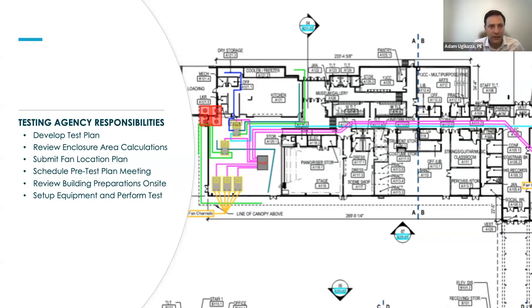So in that background in the slide, you can see I've laid out the floor plan and where all the equipment's going to go. Now that's important, because you need to understand what doors can be shut. Sometimes you have limitations on what doors you can use for the test. So give the general contractor the location of where the doors are going to be. And then once you establish where those doors are, where's the power coming from? Typically, each fan needs its own separate circuit. So certain doors may not be okay to use, because the power source is near there. You know, there's not enough independent circuits to supply those fans with power effectively.